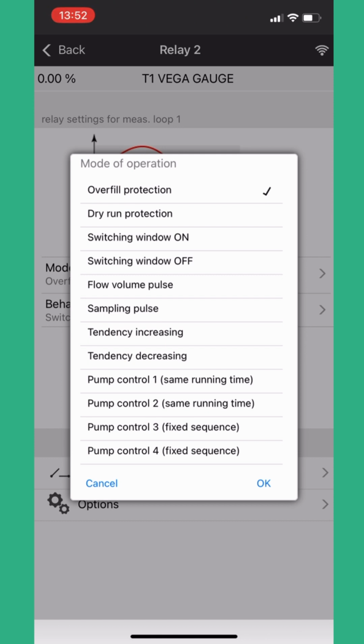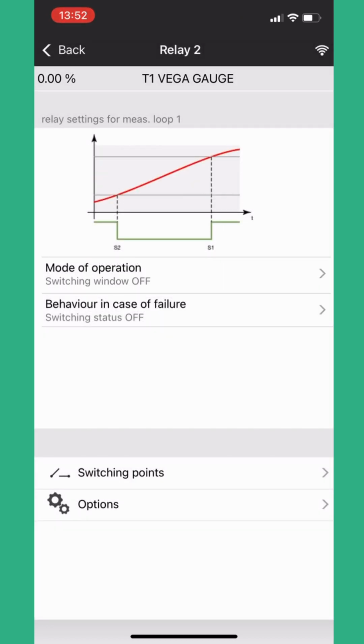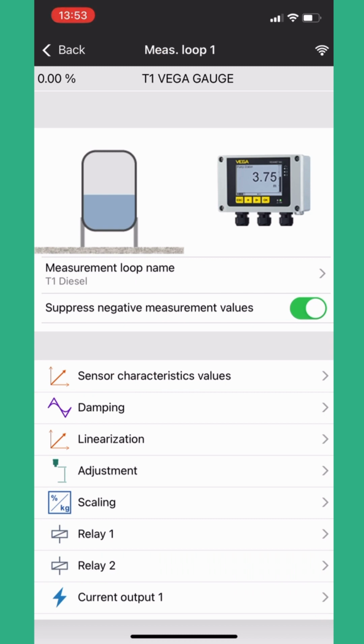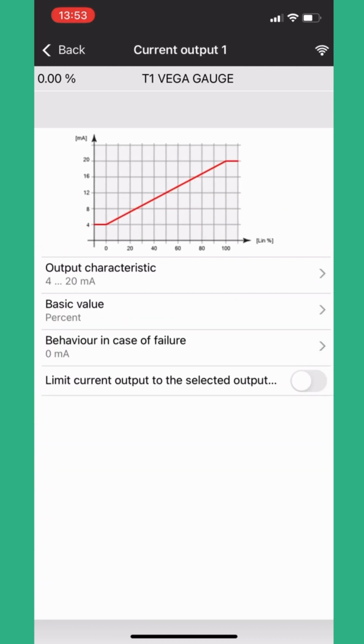We can also change relay 2, and here you can see all the options you have for the relay, multiple different options. Each one has a graphical image showing you what it means, how the relay will activate and deactivate based on levels. It's very powerful, and all the relays can be assigned to different channels and changed how they operate.